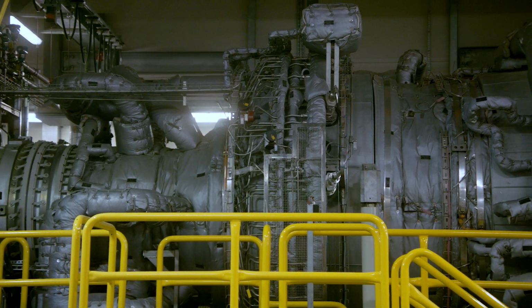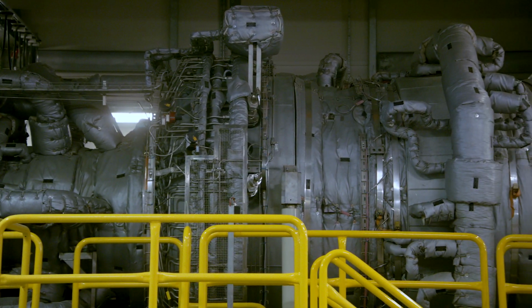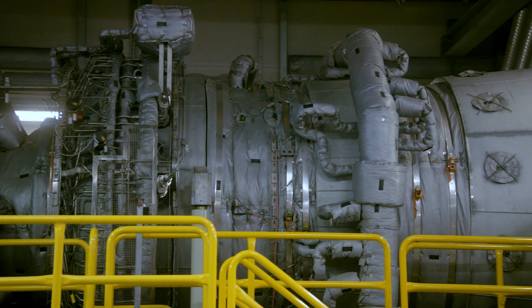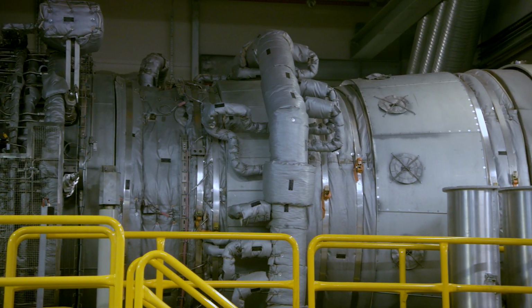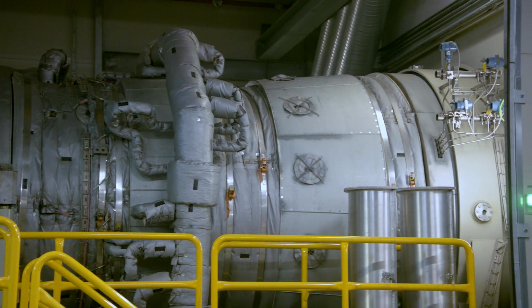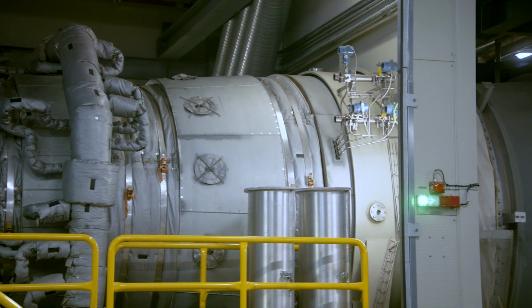So what you see behind us is the heartbeat of our Delta Energy Park plant, our combustion turbines. How this works is we draw in clean natural gas. At the same time as we're sucking air through the intake for the gas turbine, we're squeezing it down as it runs through the compressor. From there, the gas is then met in the fuel valves in the combustion chambers, creates a spark, we have a bang. That's what spins the turbine up to 6,600 RPM and turns the generator on the back end at 3,600 RPM.